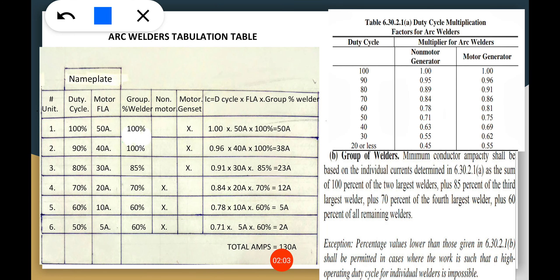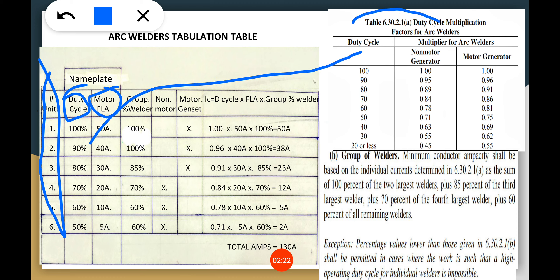We have the arc welder's tabulation table. We have 6 units here. On the nameplate we have the duty cycle and the motor FLA. The duty cycles will be referenced to Table 630.21A. The motor FLA — whoever has the largest FLA on the nameplate — that is the largest motor we define in this table.